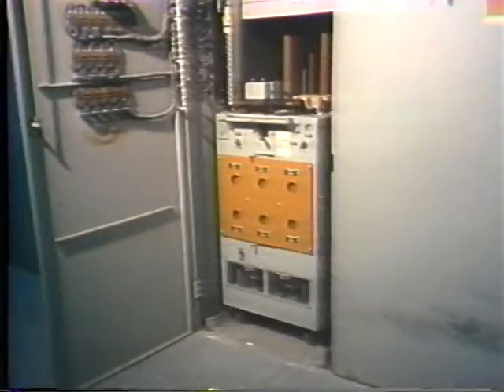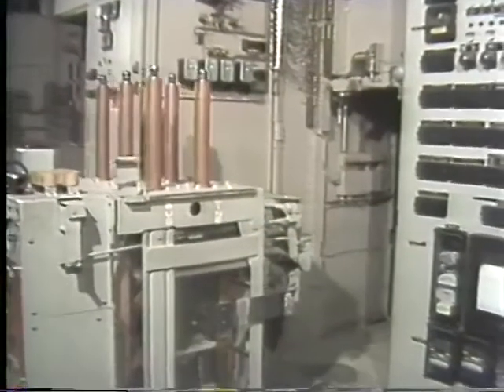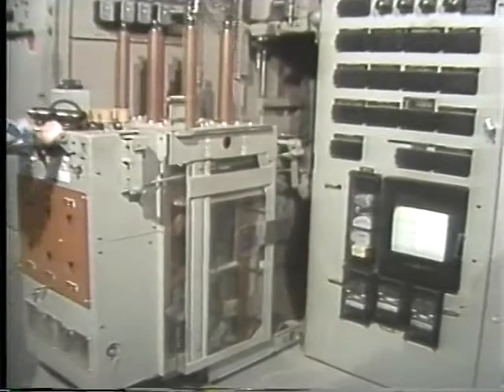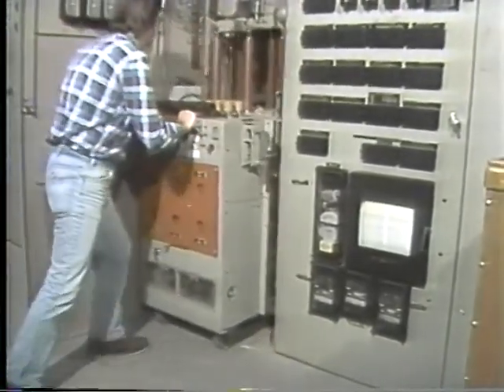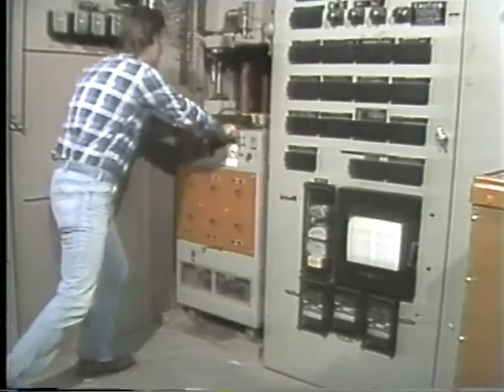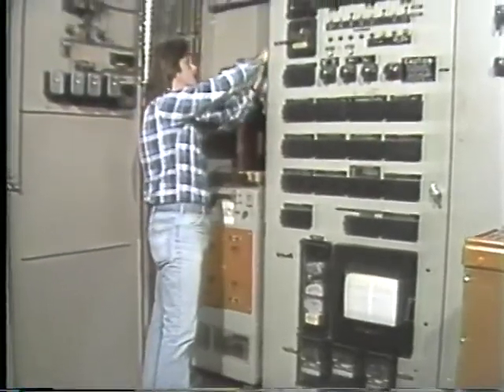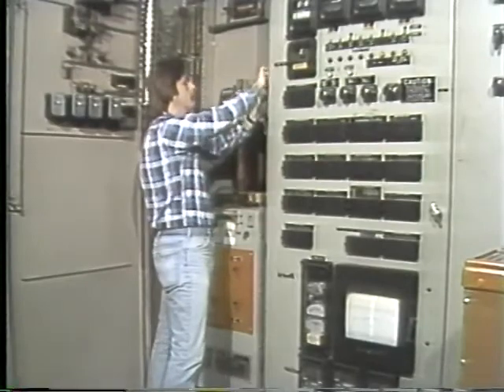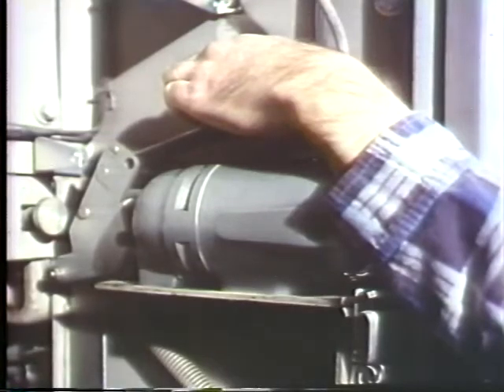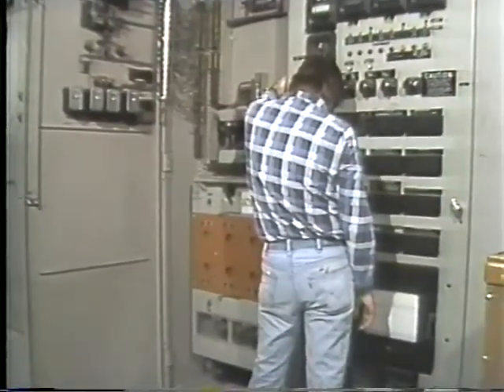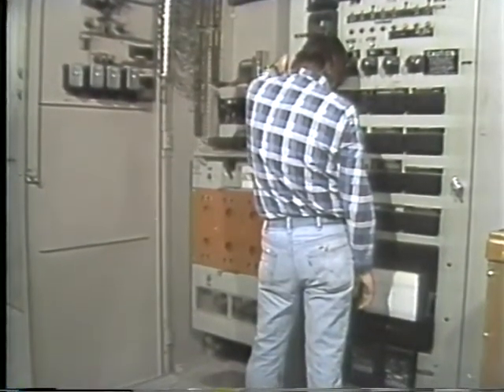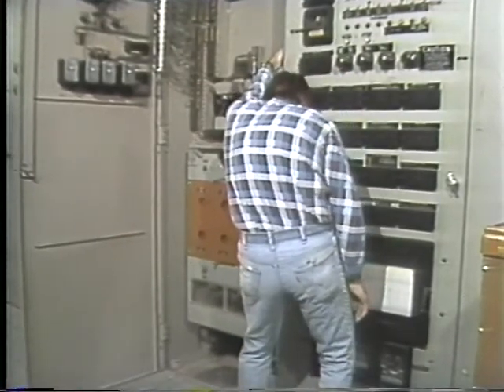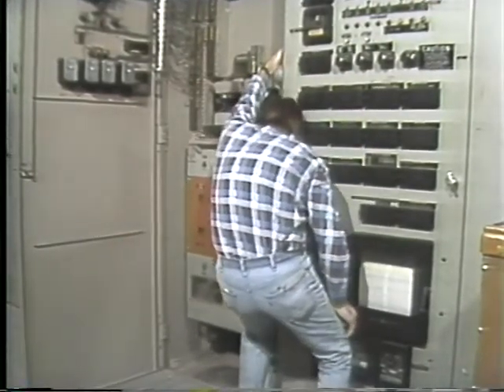This is the ground test device. It's kept in its own storage cubicle when not in use. The purpose of a ground test device is to ground equipment for maintenance or to synchronize phases when you're putting equipment back online. It rolls right into a breaker panel and racks into position the same way a breaker does. On this type of switchgear, a small electric motor is used to rack units in or out of contact. Actuating the motor raises the unit into position. For his own safety, the electrician stands to the side while he racks in the device.